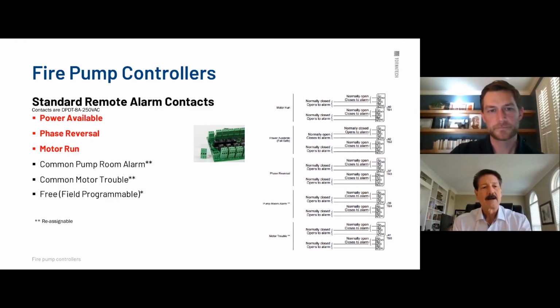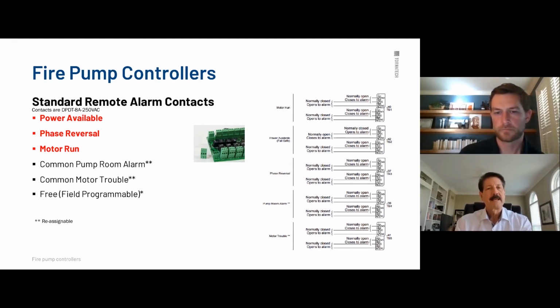Yeah, go ahead. Our double pole, double throw, like you said, two open, two closed. They're 8 amp rated, 250 volt. They're heavy duty. This is throughout our controls for diesel also. So you have the ability in some cities that require not only the remote alarm for a local alarm panel itself in the lobby of a building, but a distant remote panel. So having two open, two closed as standard really fulfills that requirement.